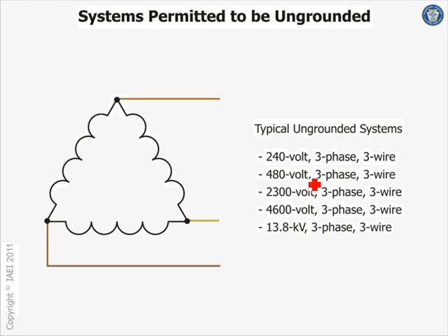You go higher than that, that's now in the medium voltage. So if you're in a single line, 99% of the time, your single line is running at 240 ungrounded or 480. Yes, sir. Is there no such thing as a 208 volt power system? There is. That would be a grounded system. Yeah, then you have to ground it, even though you don't use the neutral for a power system.